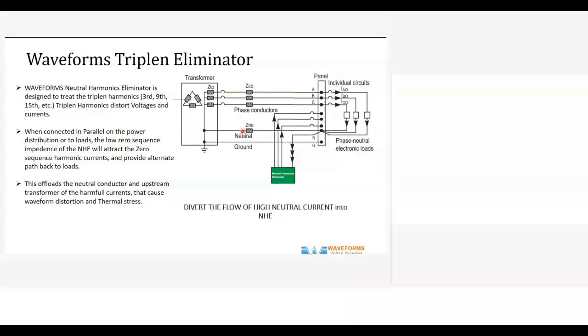Again, this is to explain how the neutral currents flow through this neutral harmonic eliminator, then flow through the winding, and go back to the load. They get cancelled because of the way the windings are bound, which we call zigzag winding. The third harmonic is phase shifted by 180 degrees, so once they are at 180 degrees, they cancel out. The phase wires and the neutral are offloaded of the third harmonic current, so there is much less heating in cables.